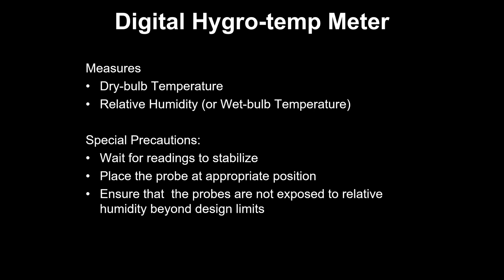So it has happened that despite having hygrometers of 2-3 types, we used a psychrometer to do the temperature and RH measurement at some places, because there was a lot of water, especially in the chill water system where the chill water is directly sprayed. So humidity measurement is not possible. Within a minute, the instrument will show a 0 reading. Take it outside, dry it, and the probe will again start showing. So it doesn't damage the probe, it just doesn't show the reading. So you have to see that you are operating within those limits.